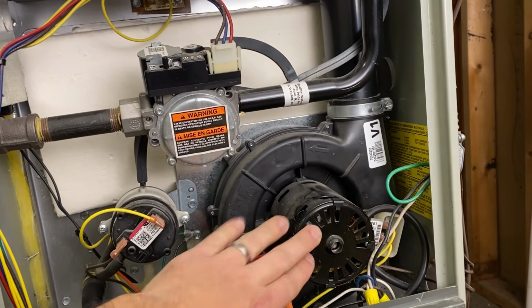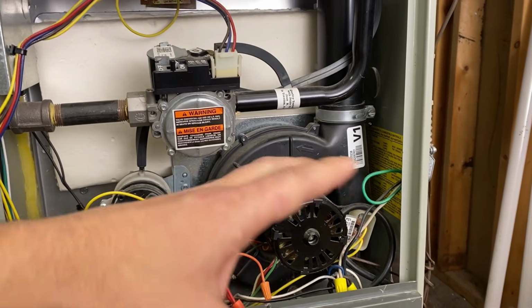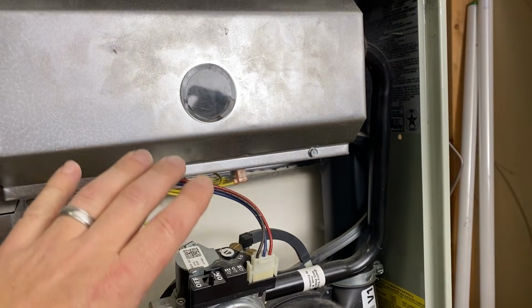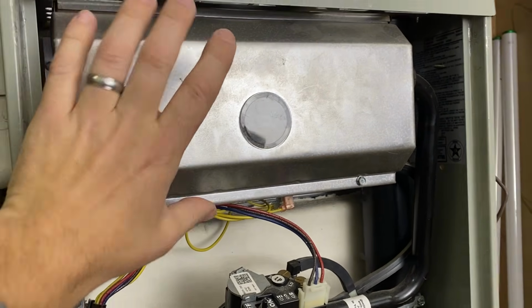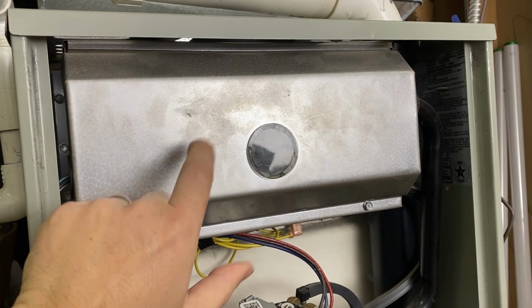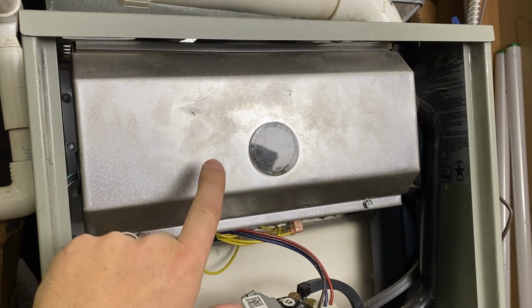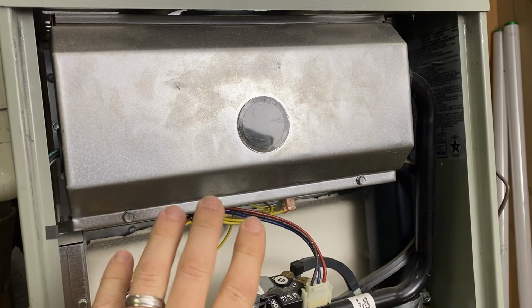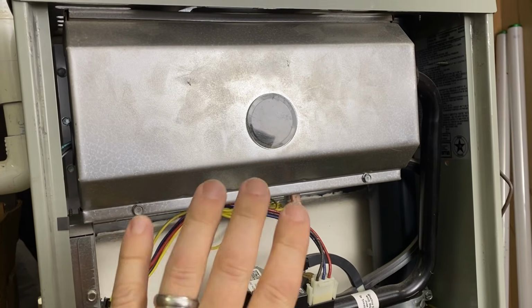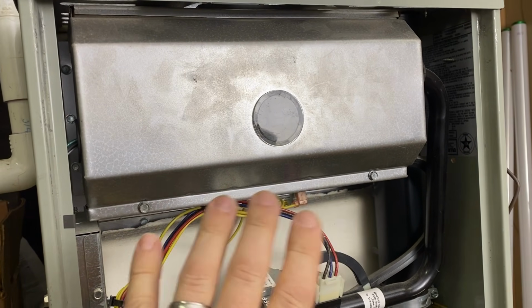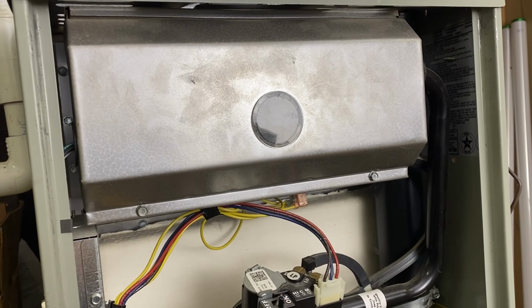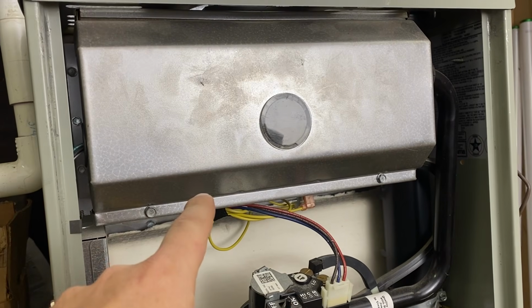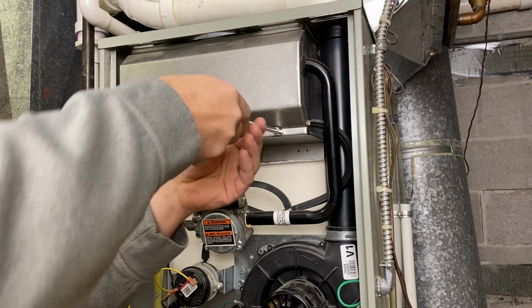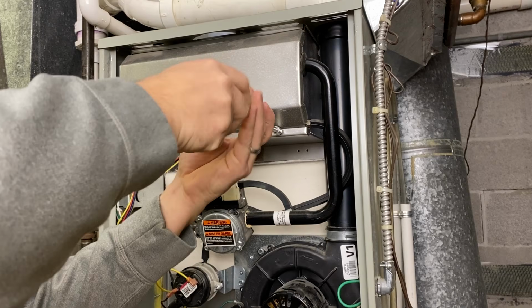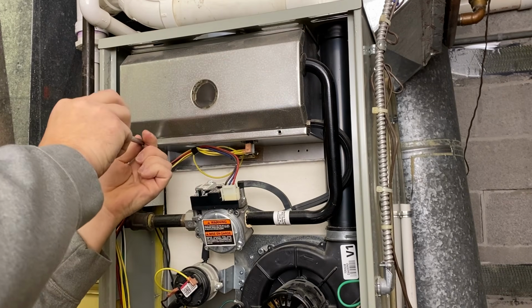If you're getting past this point where the blower comes on, the next thing that's going to happen is your burners are going to light. So let's take the cover off of this so we can see inside a little better with the camera. There are two or three components in there that we'll need to check in order for the burners to light. If you're not getting flame, you're not getting anything lighting, this is probably where your problem lies. Generally, it's just a couple of sheet metal screws here that we'll take out.